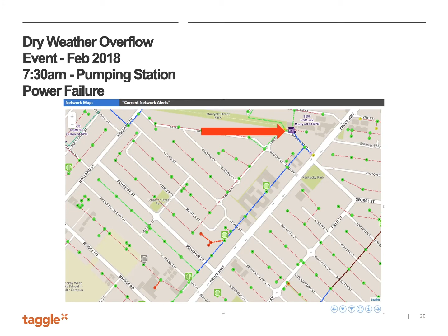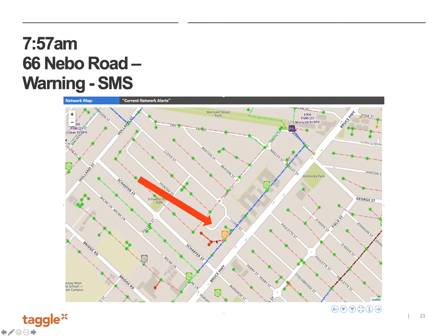The event seems to start about 7:30 in the morning. About 30 minutes later, this sewer manhole sensor starts sending an alarm saying the pipe is full. So what's happening is this wet well is filling up and backing up through this pipe here, and this alarm is starting to show there's a problem.